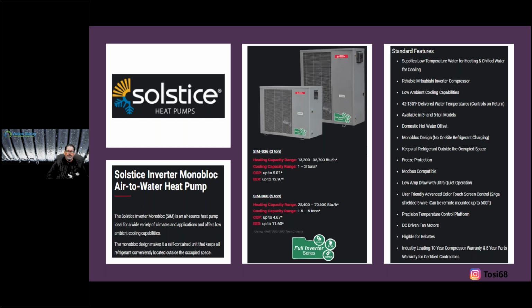So lowering water temperature is a must here. Maybe you just want to do a partial load, running this for the majority of our heating season when it's mild out. And then, hey, I can incorporate the existing boiler as a backup for when it's colder and I need something more than 130.